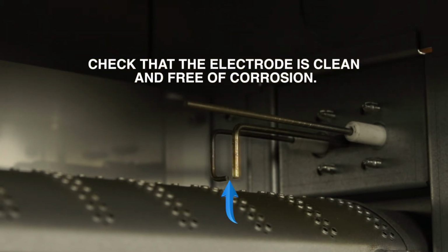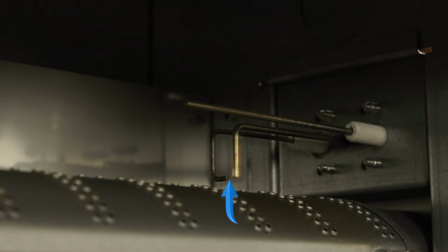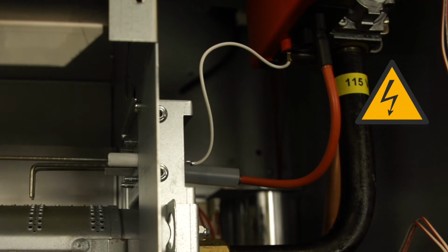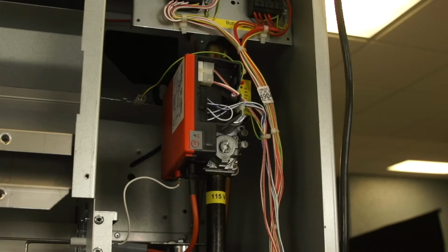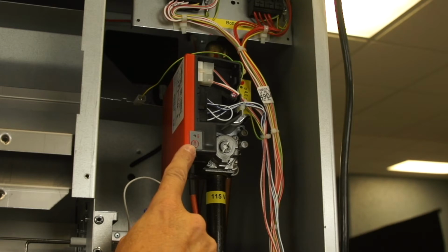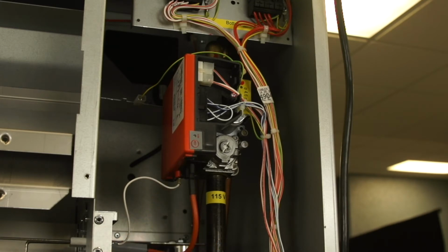Also, check that the electrode is clean and free of corrosion, and that the electrode's high voltage wire is tightly connected to its terminals at both ends. If the spark gap and high voltage wire are in order and no spark is present during an ignition attempt, we recommend that you replace the ignition module. If yes, go to step 3.